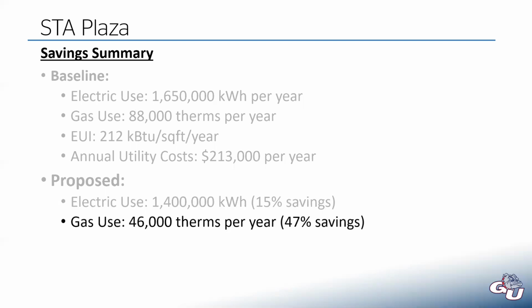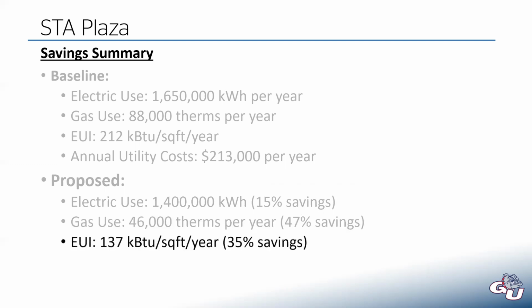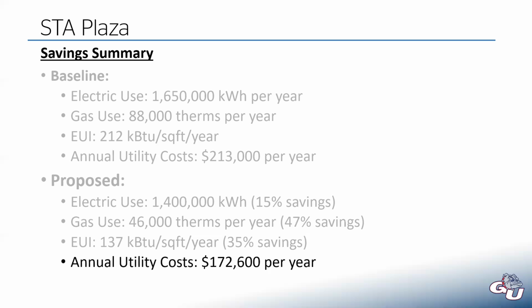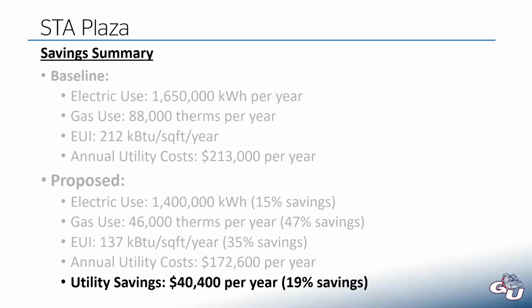On the gas use, however, we dropped their use down to 46,000 therms per year. We saved almost half of their gas bill. And that's almost entirely owed to that demand control ventilation strategy. Well, it's not entirely true. A good chunk of that is probably also attributed to implementing a schedule and turning off those multi-zone units, especially during those unoccupied hours. Their new EUI is around 137, or about 35% savings. That's pretty dang good. And at the end of the day, their new bill is around 172,000 a year, and we save them about $40,000 per year, about 19%.